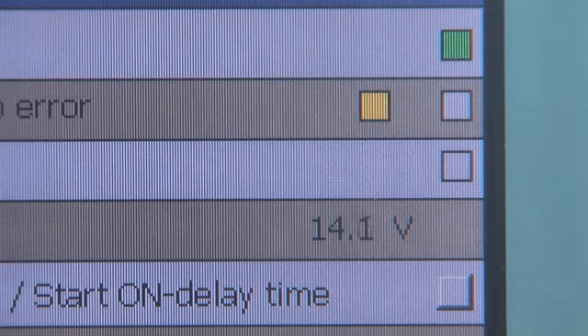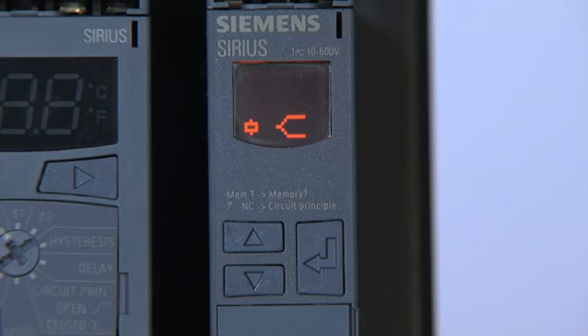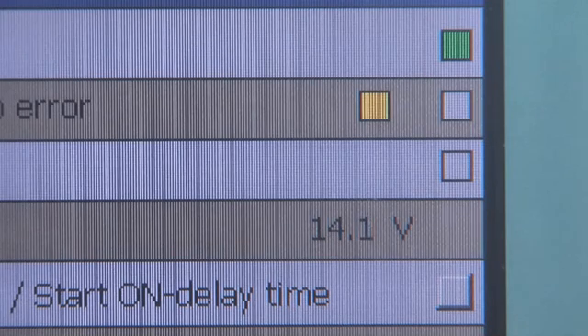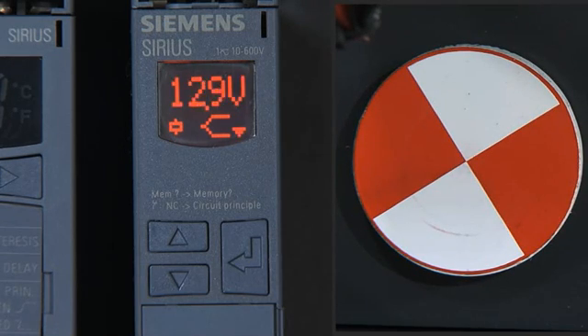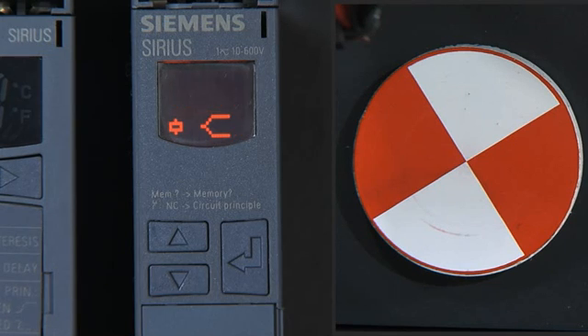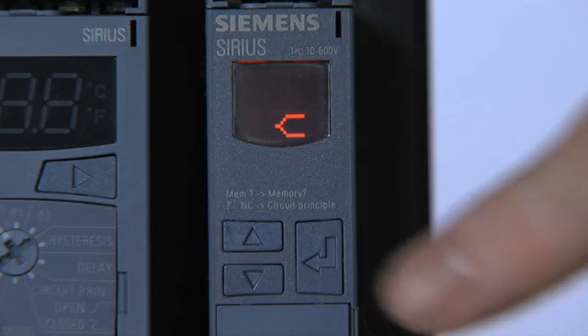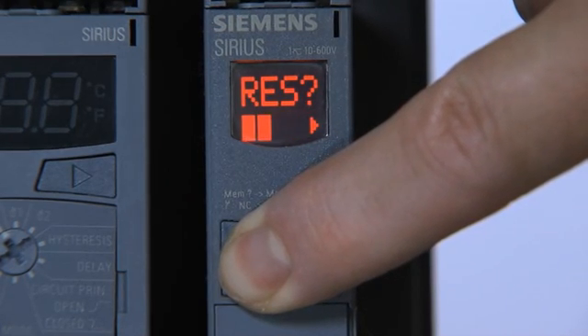If the voltage drops below the set warning threshold, this is signaled on the device and via IO-Link to the controller. If the voltage drops further below the shutdown threshold, the trip delay time starts to run. The motor is only switched off after this settable time has expired. The fault can be acknowledged on the relay or via the controller depending on the set-reset behavior.